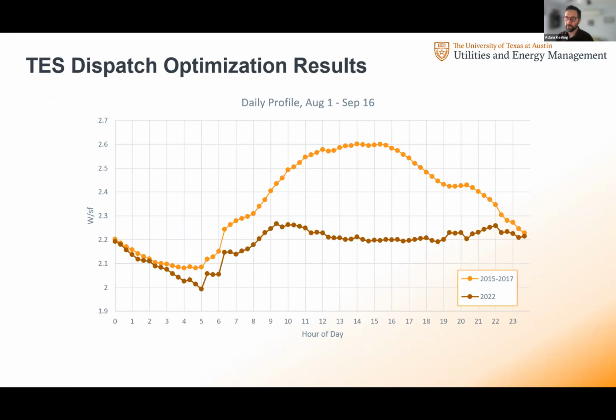Quick graph on some results from the thermal energy storage, or TES, which was built in 2017-2018. This is a daily profile from peak season, early August to mid-September, showing watts per square foot for main campus. As expected, without thermal energy storage, shown in orange, it dips down in the middle of the night and peaks in the afternoon. With the thermal energy storage tanks, we've been able to pretty much completely flatten that load through the day. A lot of that has shifted to night, but the night level hasn't really changed much since things have also gotten more efficient.